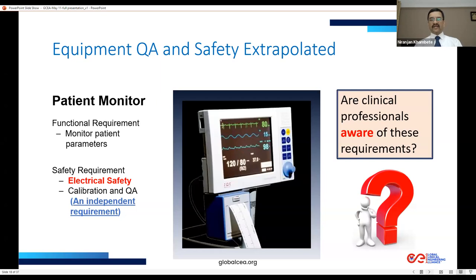As I said in the case of surgical scalpel, safety requirement could be independent, and that is also true here in the case of patient monitor, where electrical safety is independent of functional requirement. One can say calibration is linked with the functional requirement, but the patient monitor may be perfectly working, showing some values, but they may not be correct. So just looking at it, one would say it is functionally okay, but unless you do calibration and QA, we can't say it is safe to use.